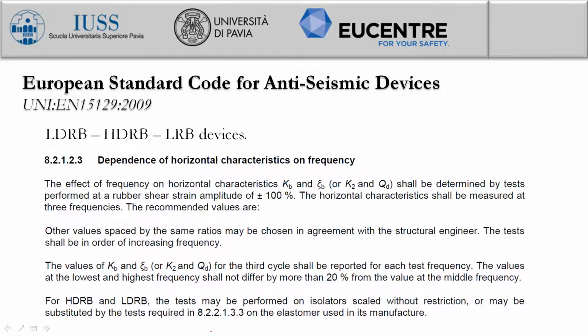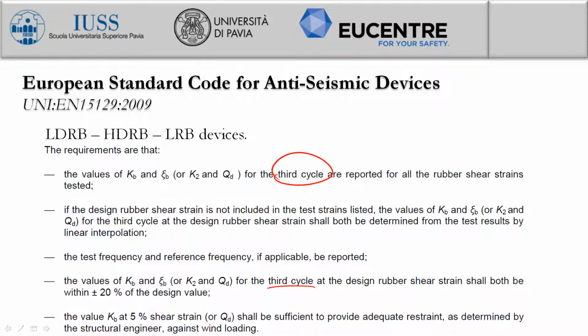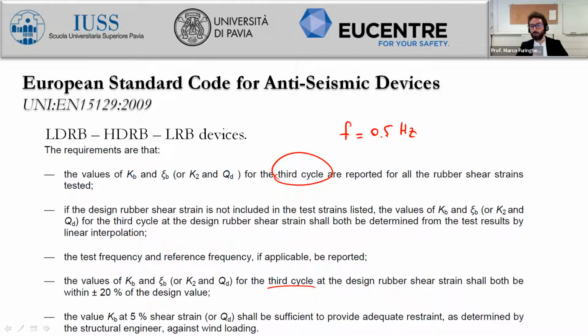Professor, one question, sorry. Yeah. Yes. What is the frequency for the test that is specified in the document? Either it is defined by the structural engineer or it could be equal to 0.5 Hertz. Thank you. You're welcome.